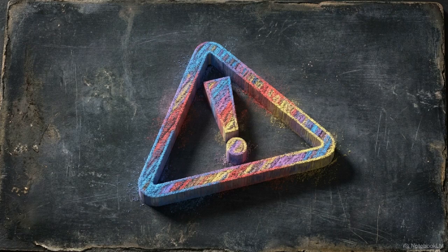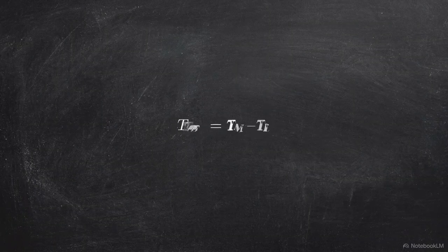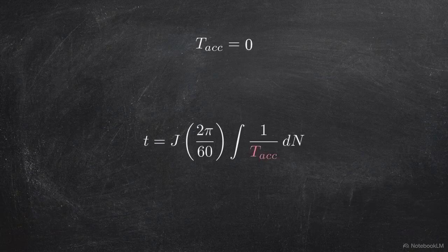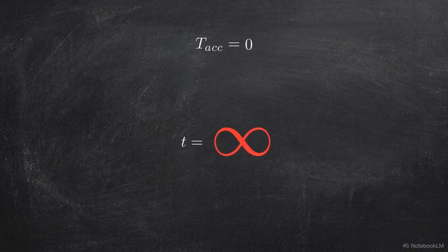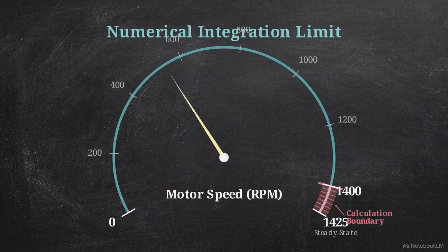There is one vital rule to remember. Never attempt to integrate to the exact steady-state speed. If the torques match perfectly, your acceleration torque becomes 0 and your time becomes infinite. In this case, we stop our calculation at 1400 RPM.